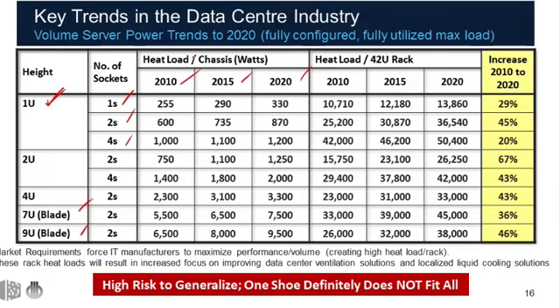What this is showing is here's the heat load, actual heat load, if it's fully loaded - that's the amount they'll draw. So it went from 255 for a 1U, 1 socket, to 330 in 2020. Again, our track record is really good on predicting what it will be. We predicted in 2005 to 2010 that all came true.